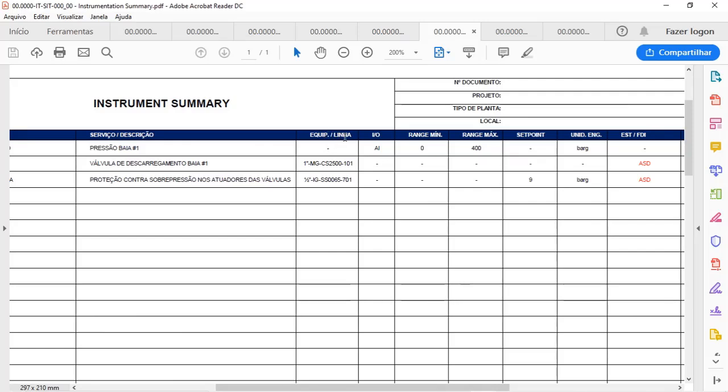You will inform the instrumentation team the minimum and maximum range of that instrument, and sometimes the set point and the engineering unit, in order that the instrumentation team can do the specification of an instrument.